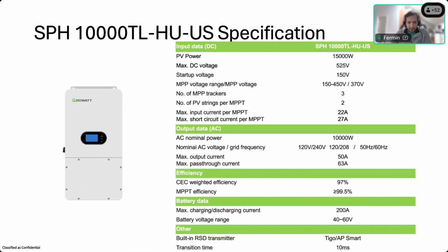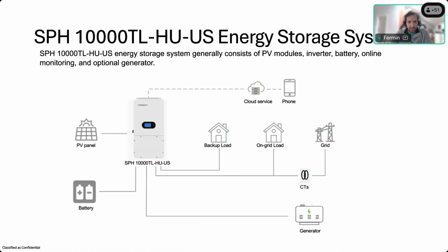As I mentioned before, it supports 48 volt battery systems, and it comes with a built-in RSD transmitter. Same as the MIN inverter, you have the option to order the Tigo or the APsmart transmitter that is compatible with the same devices as the MIN inverter. It's also UPS rated, meaning the transition time between on-grid and off-grid is only 10 milliseconds. I think Tyler mentioned it before, but it comes with an integrated ATS, so you don't need to install a separate ATS for home backup.